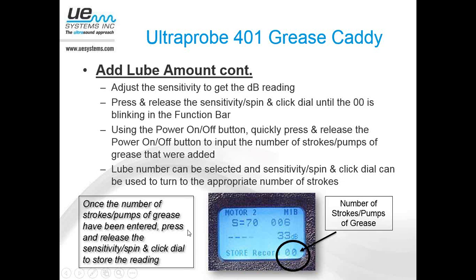Then once the number of strokes and pumps of grease have been entered, you'll press and release the sensitivity spin and click dial to store the reading just like you normally would. And so it'll store the decibel level reading along with the number of strokes of grease that were added.